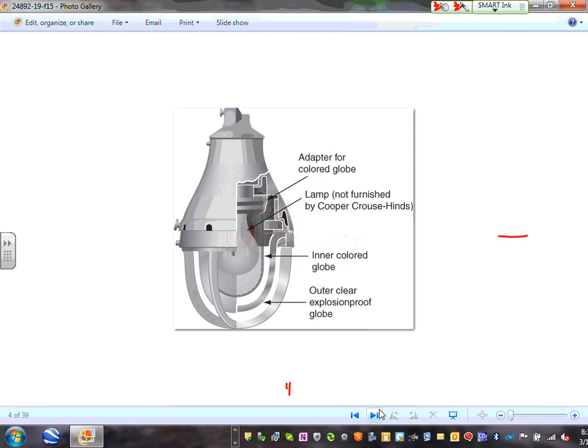Look at the lighting fixture, Karen, that they do. They have globes in a globe in a globe. So that's how they contain it, guys. We have an outer clear explosion-proof globe, then an inner colored globe inside. Can you see that? Lamp inside it, an adapter for color. So the temperature, guys, right here, because they have two globes, the temperature would not be a whole lot in there because they contain it. And it can contain an explosion proof inside this fixture.